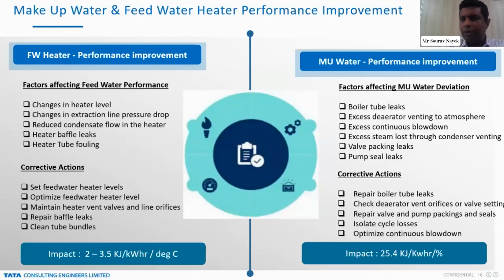Now, what are the corrective actions? We should always look into optimum boiler operation, so that boiler tube leaks are minimized. The deaerator vent orifice and the deaerator vent losses are minimized. The valve and pump leakages are also kept to the minimum level, and continuous blowdown also has to be minimum, so that our makeup quantity is minimized to improve the heat rate. If we look at the feed water heaters, from the top feed water heater to the lower feed water heater, almost 2 to 3.5 kilojoule per kilowatt hour impact is there on the heat rate. Similarly, for the makeup water, 25.4 kilojoule per kilowatt hour per percentage increase in the makeup water quantity, the heat rate will be affected.